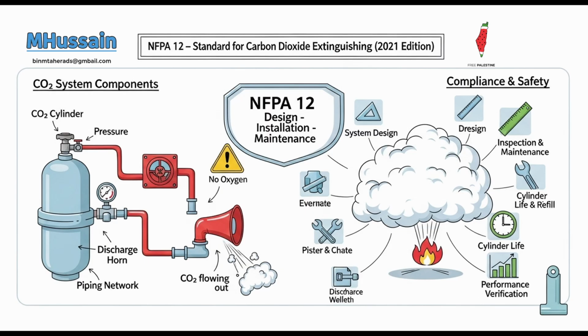For valves, they must be listed or approved and capable of withstanding the expected pressures, such as an 1800 psi, 12,411 kPa, hydrostatic test for low-pressure systems. They also must be protected from mechanical damage, as a compromised valve means a compromised system. Listed, tested, protected valves. Now the nozzles, that's where the CO2 actually sprays out.